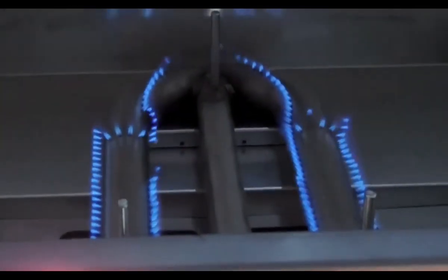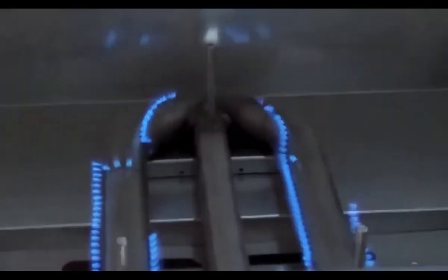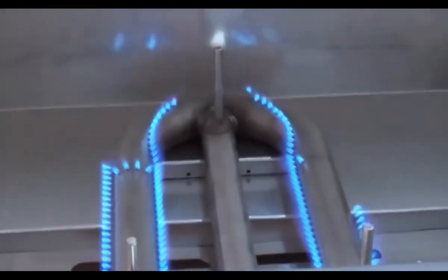Adjust the air shutter too far open and more air mixing with the gas will blow the flames off the burner so flames appear to float. Air flow will blow some flames out so we do not have an even row of flames.